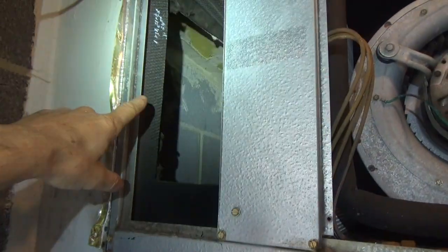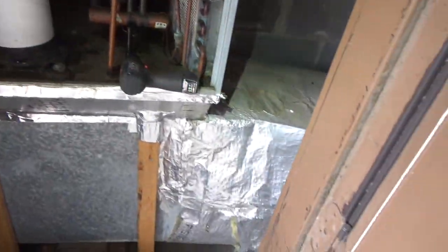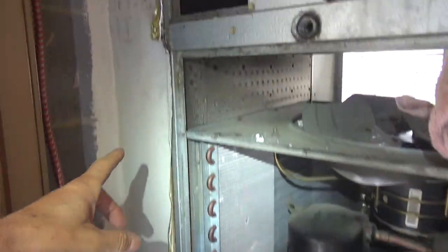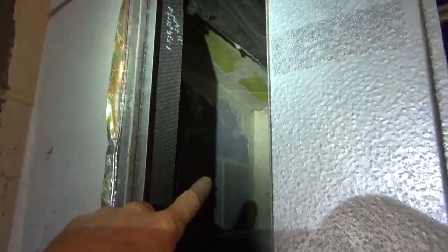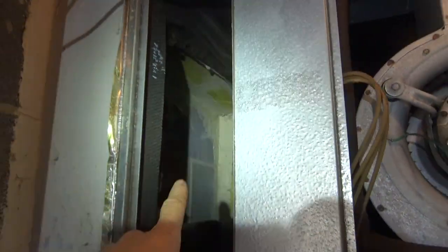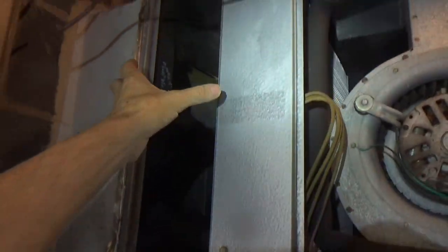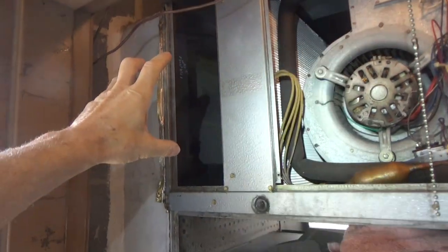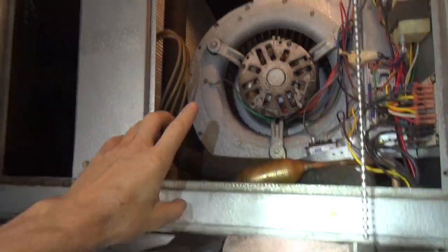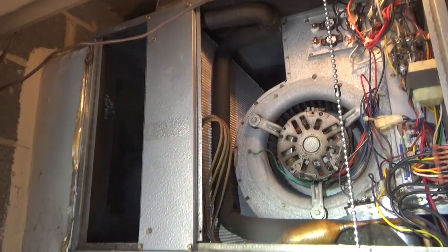They used the original large ductwork on the bottom, and then they went 6x30 on the side with a large hole there rather than hooking a small flex to the skinny hole. And with good airflow, it keeps pressure down on your coil and makes it last long.